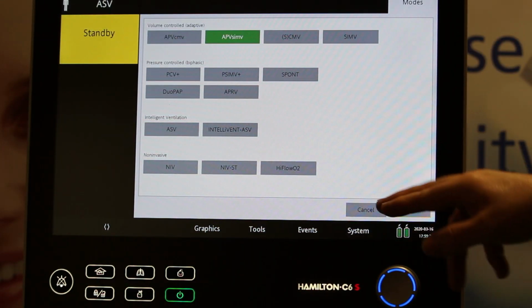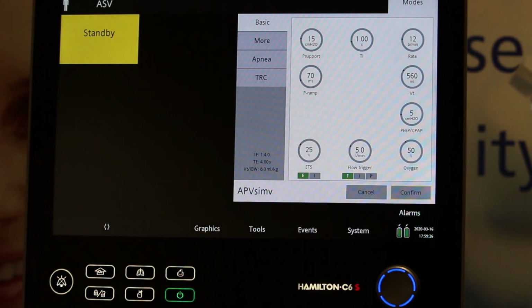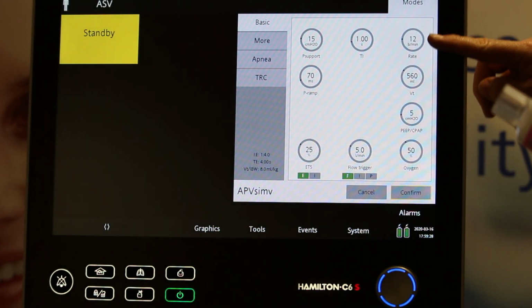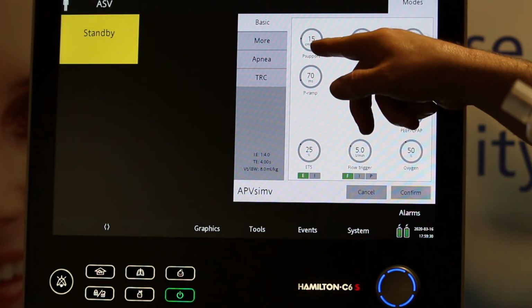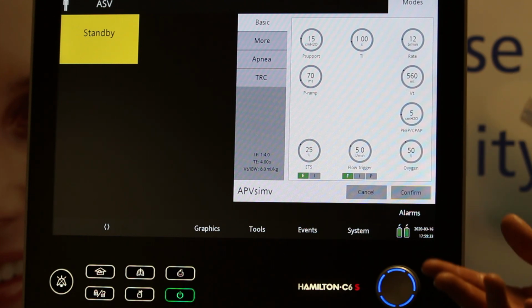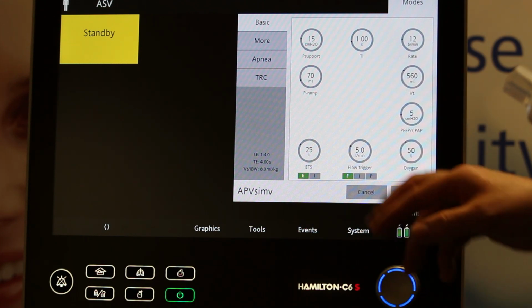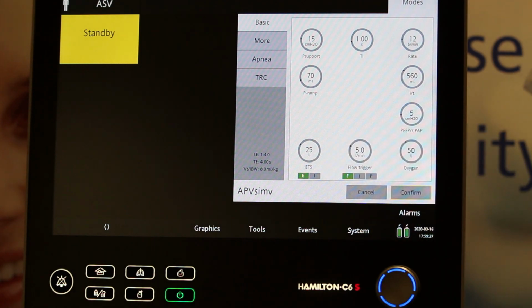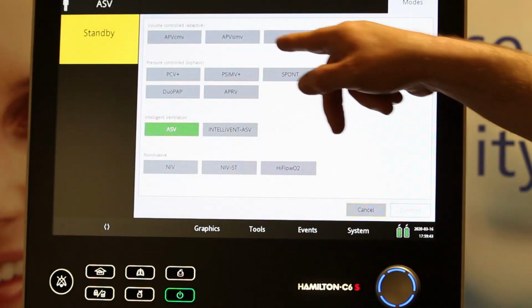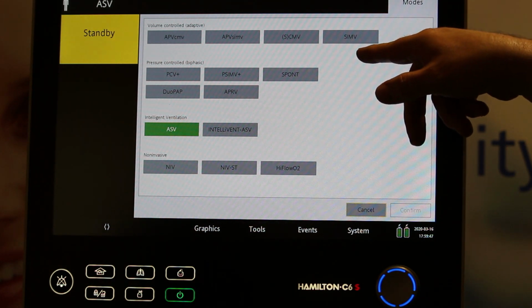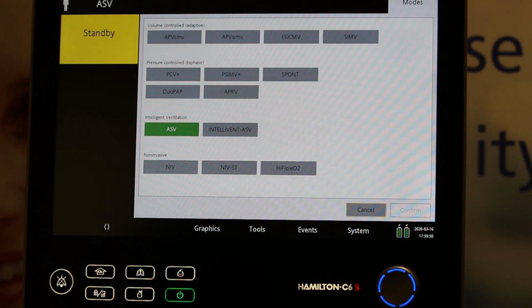Then APV SIMV, synchronized intermittent mandatory ventilation. Again, all the same settings, but we do have pressure support in the mode, so it will synchronize with patient activity. And also we can set our expiratory trigger sensitivity and all the other settings that were in CMV. So that is APV SIMV. And here moving on to CMV and SIMV, again there's no APV in the algorithm, so it's not trying to manage the pressure, it's just guaranteeing a volume.